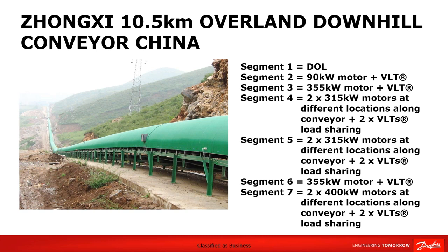Segment four, there were two 315 kilowatt motors. They were at different locations along this conveyor, and two of these VLTs were applied as load sharing. Segment five, again, two 315 kilowatt motors at different locations along the conveyor, and again, two of those VLTs had load sharing. The sixth segment was a 355 kilowatt motor and a VLT, and then segment seven, two 400s at different locations along the conveyor, and again we had load sharing between two of them.